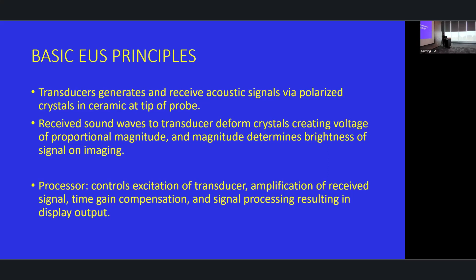And the take-home point is that the tip of the endoscopic probe has little crystals in it. Don't bang it around. Don't knock it around. They're very sensitive, and if you damage the tip of an ultrasound probe, it can really cause issues with acoustic interference and poor image generation. So the tip of the probe is very sensitive and needs to be handled delicately.